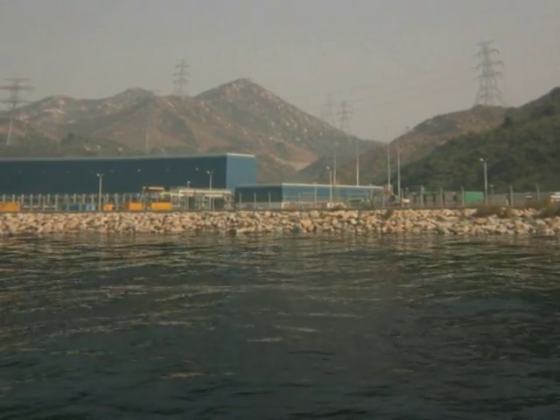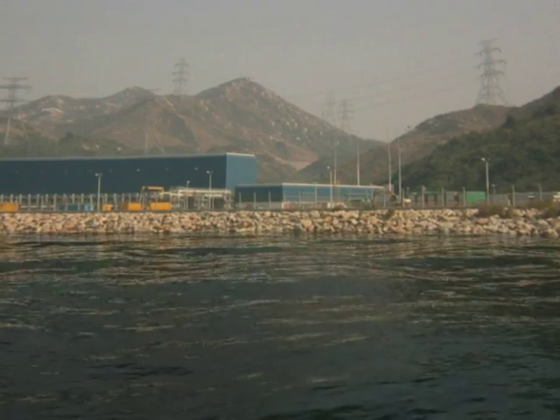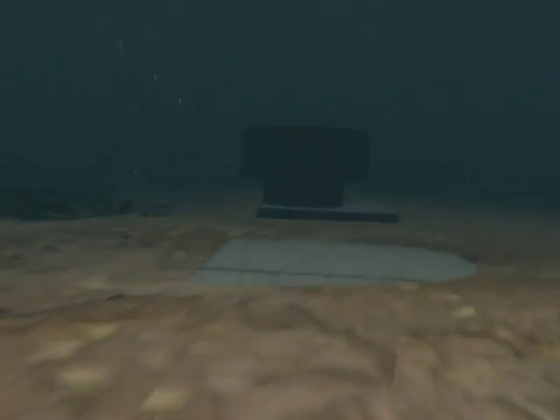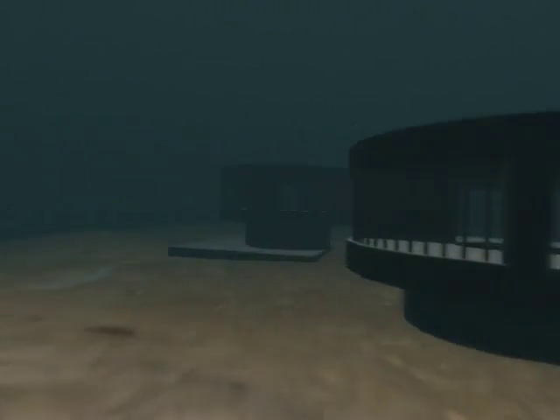Renovation of Black Point's cooling system was essential due to the extent of the marine growth within the culverts. This restricted the flow of cooling water, especially at very low tides. The station uses a siphonic once-through direct cooled system with a submerged offshore intake. Cooling water is taken from the sea by the two intake culverts.